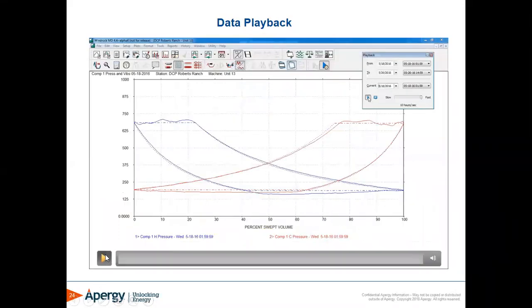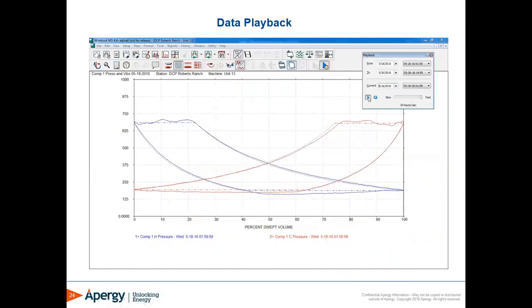This slide we can actually play. So I'm going to hit the play button. We'll go from no leak. We'll see the PVs spread apart during the leak progression. Then you'll see a skip from the leak progression to where it's back to normal.